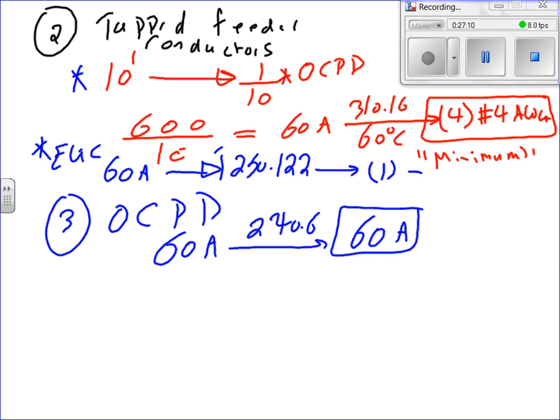If you go there, what do you get? One conductor number 10 AWG. I need that one, right? 4 conductors for the 3 phases and the neutral, and an equipment grounding conductor, unless I'm using EMT, rigid, intermediate, any of these metallic raceways. Why did I do the overcurrent protection device first, guys? Because how would you size the equipment ground conductor? You need the overcurrent protection device, don't you?